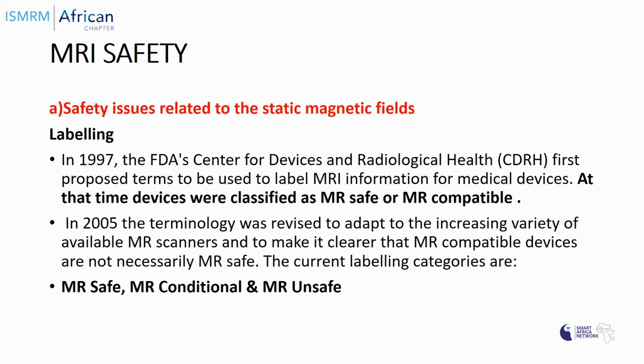Now, another important thing we have to talk about is labeling when we are considering safety issues related to the static magnetic field. In 1997, the FDA Center for Devices and Radiological Health first proposed terms to be used to label MR information for medical devices. At that time, devices were classified as MR safe or MR compatible. In 2005, the terminology was revised to adapt to the increasing variety of available MR scanners and to make it clearer than MR compatible devices. They are not necessarily MR safe.